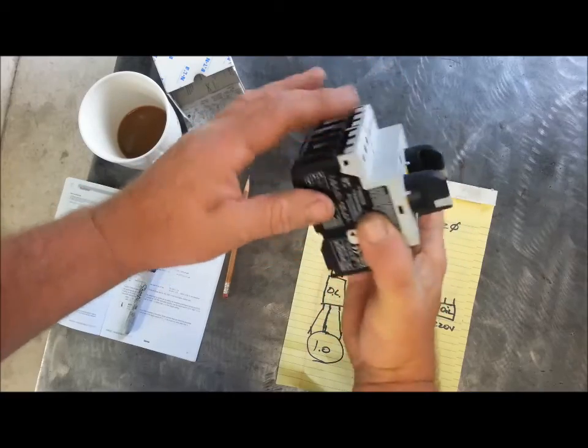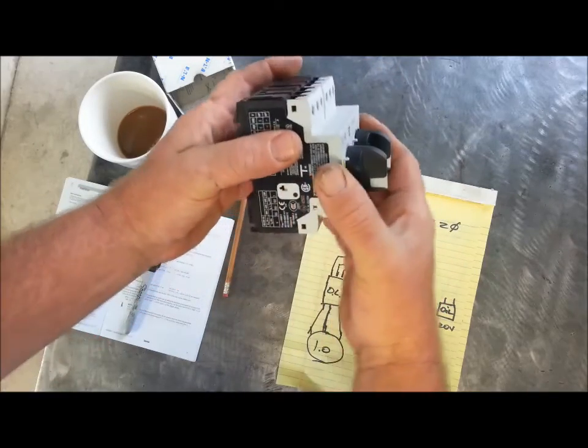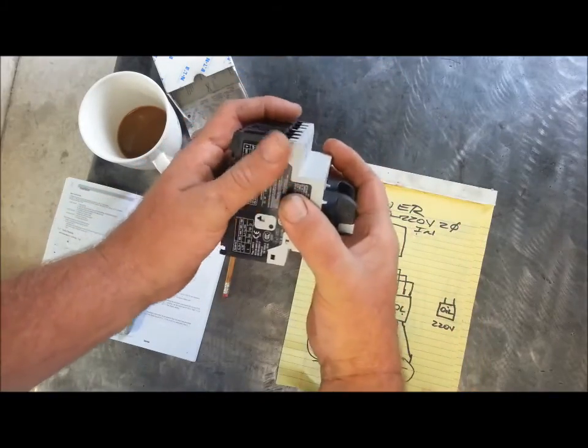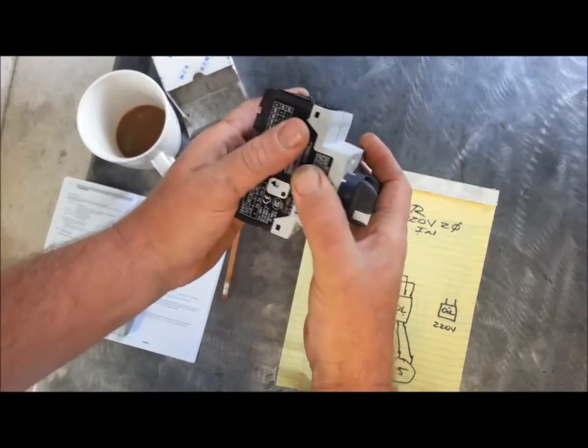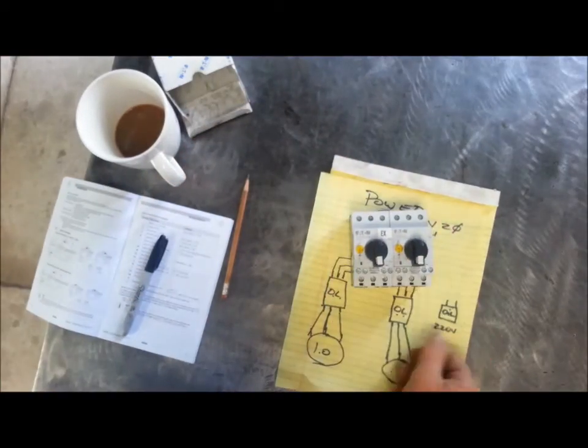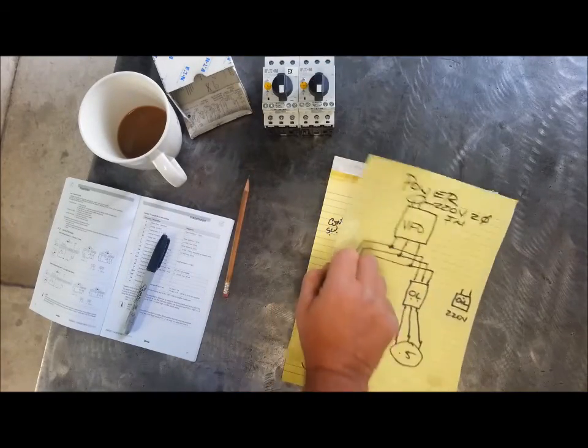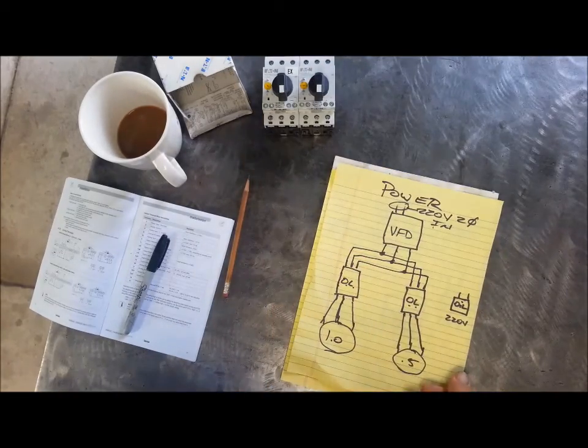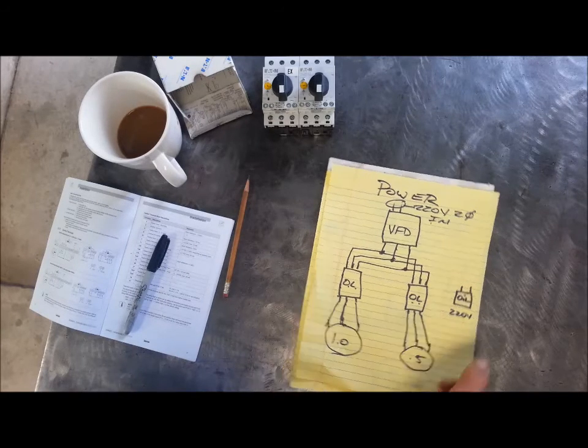These don't run hot, so you don't have to worry about venting the enclosure. The VFD is the only thing that has a heat sink and has cooling requirements. So the VFD will need to be out in the open, but protect it from grinder dust. Put it down inside the cabinet or somewhere out of the way where it's not going to pick up a bunch of grinding dust. They are enclosed on the top. There's no chance of anything getting in the top of them, but they are vented on the sides.